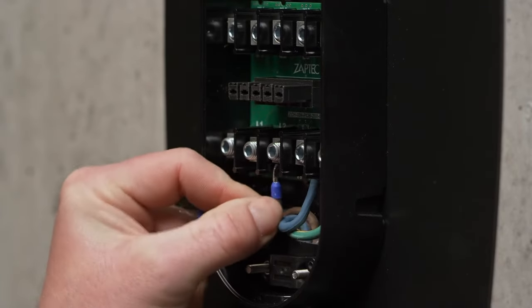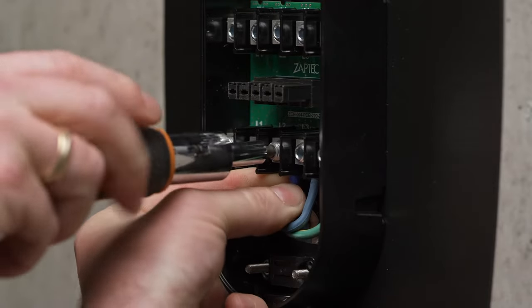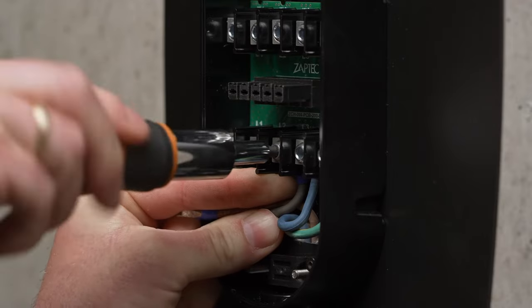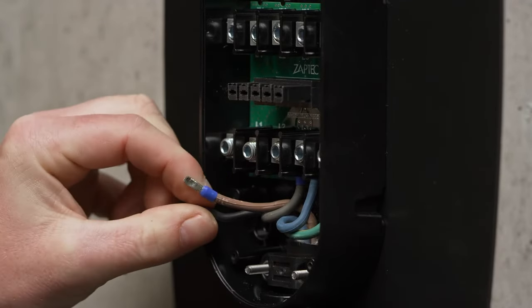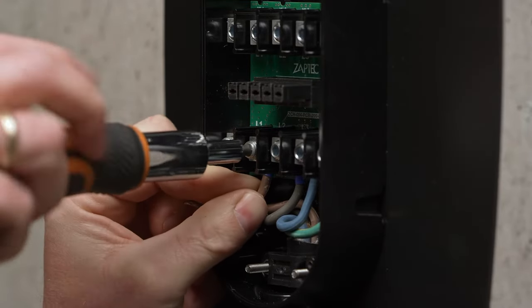You can now connect the wires in accordance with the wiring diagram, which can be found beneath the junction box on the back plate. It is important that you use a torque tool to tighten the coupling screws. Remember to check that the sealing cone has been installed correctly in accordance with the installation manual.